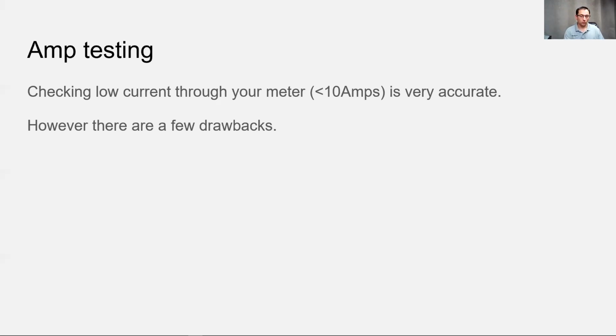But talking about your meter and running current - opening up a circuit and putting your amp meter in series to measure all the current through that circuit - it has a few drawbacks. First of all, you can blow a fuse, I'm sure you guys have done that. The meter's fused, and if you draw more than 10 amps or whatever the scale is, you could just burn up a fuse, and that's no good.